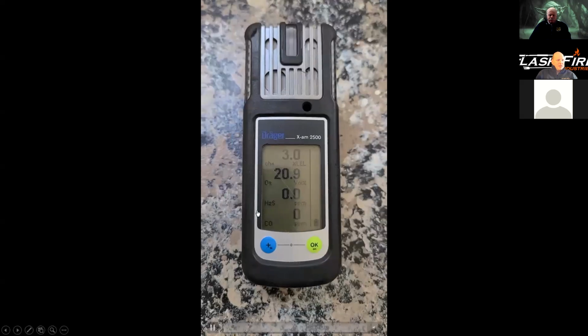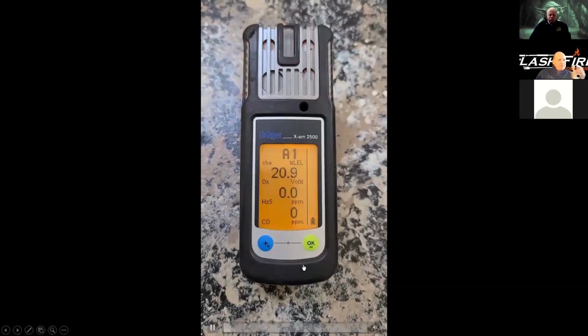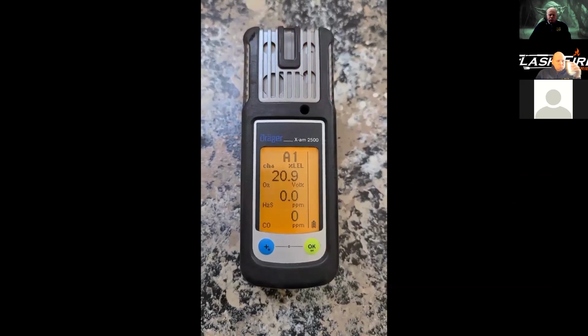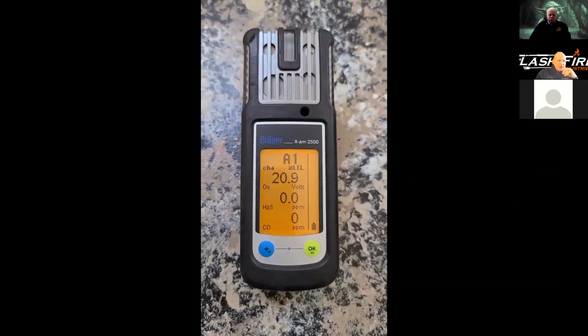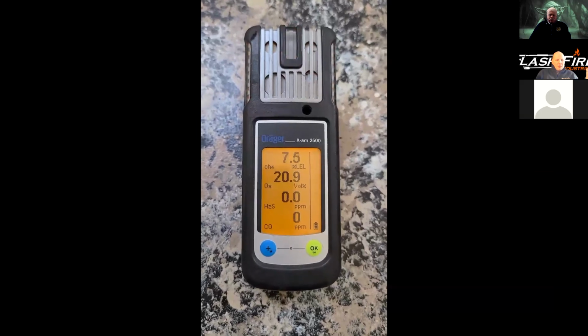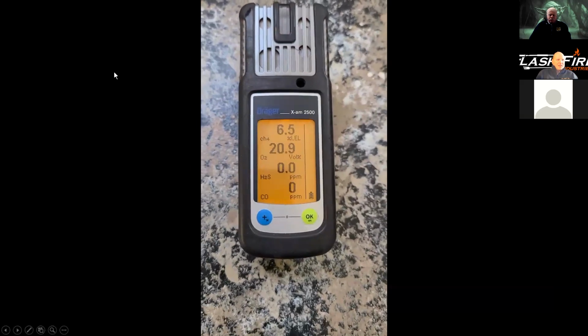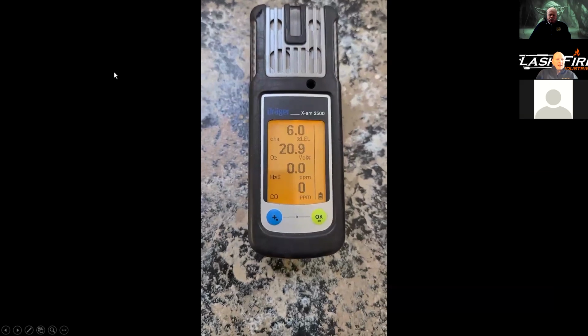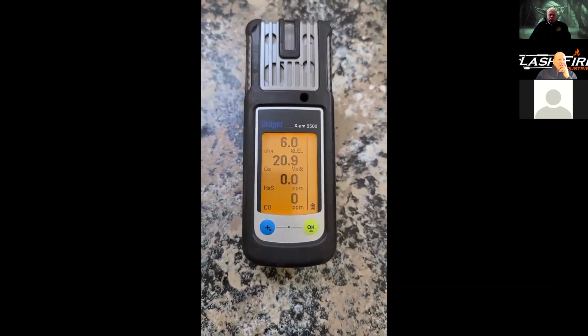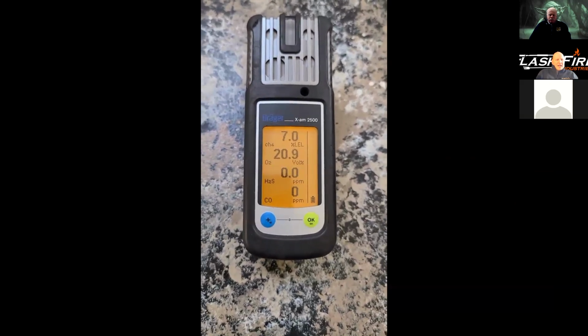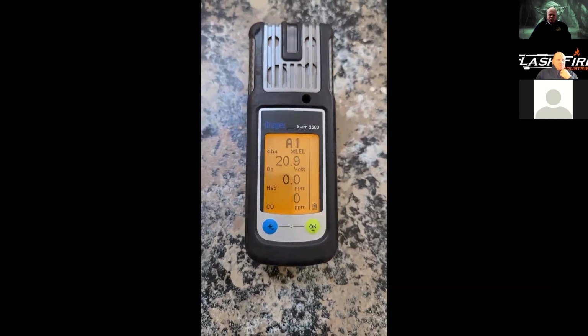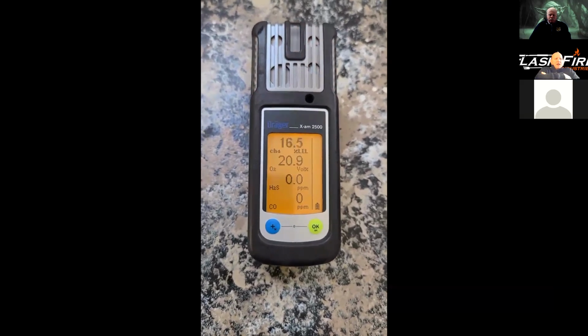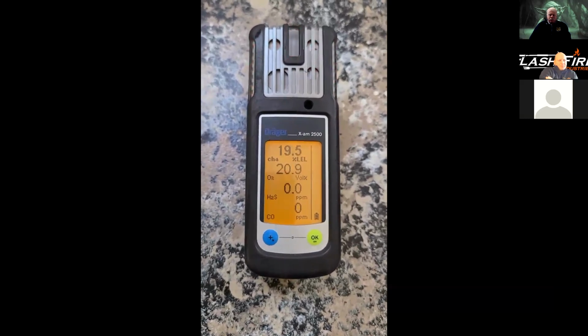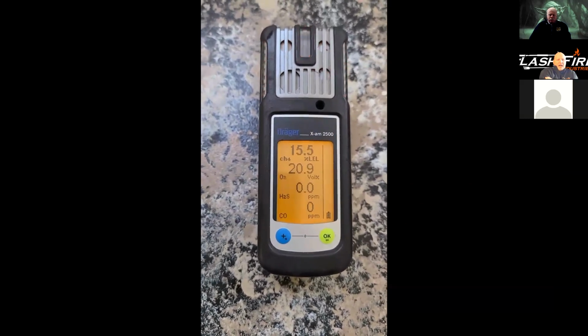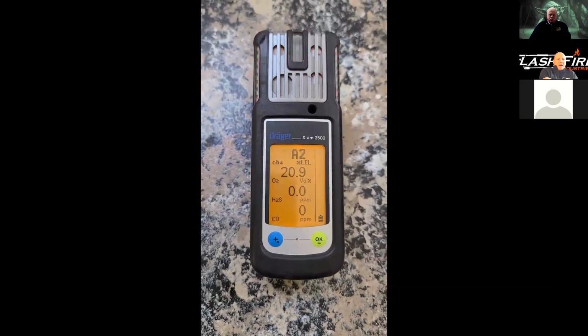All right, so this is going to be an example of the alarms. So this is that low alarm. I went into the low alarm, came back down, and it automatically silenced. So potentially, if you were talking to me, I may not have known that it went into alarm. Now I'm going to put more gas on it, and I'm going to let it go into the high alarm. You're going to see that LEL comes up about 20%.